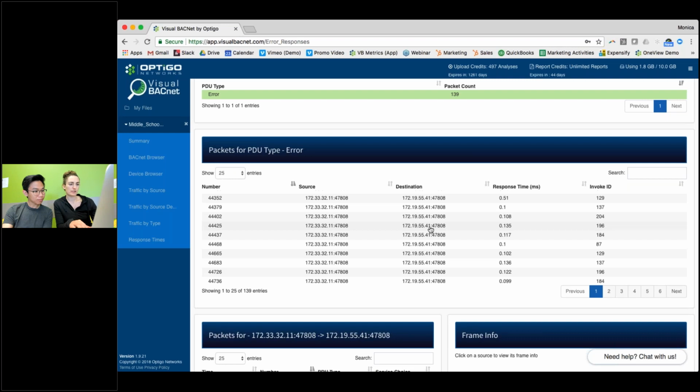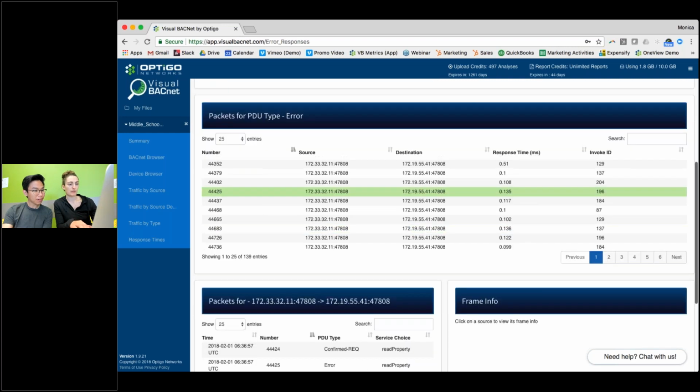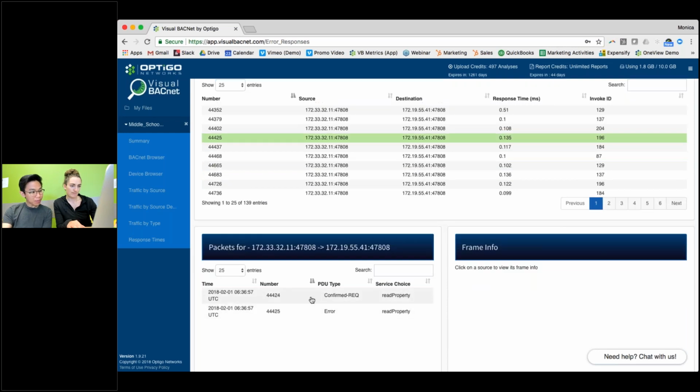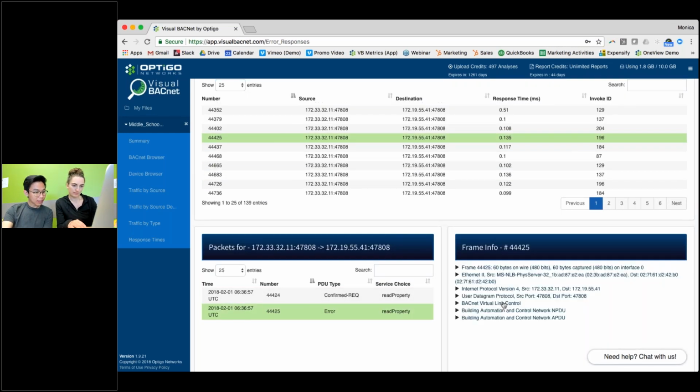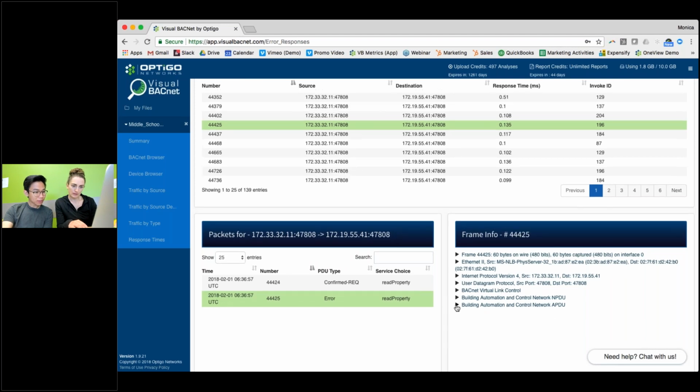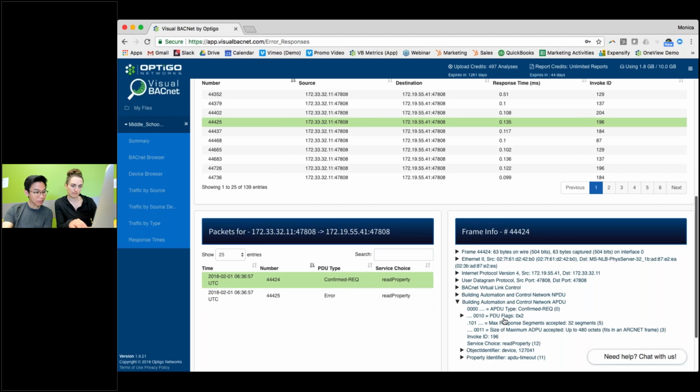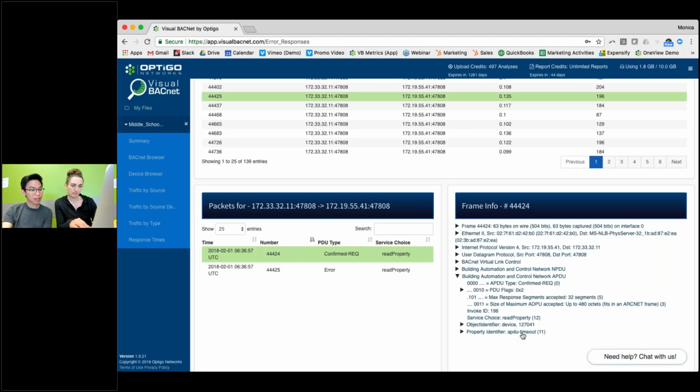This is the same one that I just read out, correct? Correct. I can't remember. Already forgotten it. Yeah. It's the read property request, and if you look at the error, APDU. So it's an unknown property. And if you look at the request, you should see what property it's trying to get. So APDU timeout property. So it's requesting the APDU timeout and it's responding with errors.